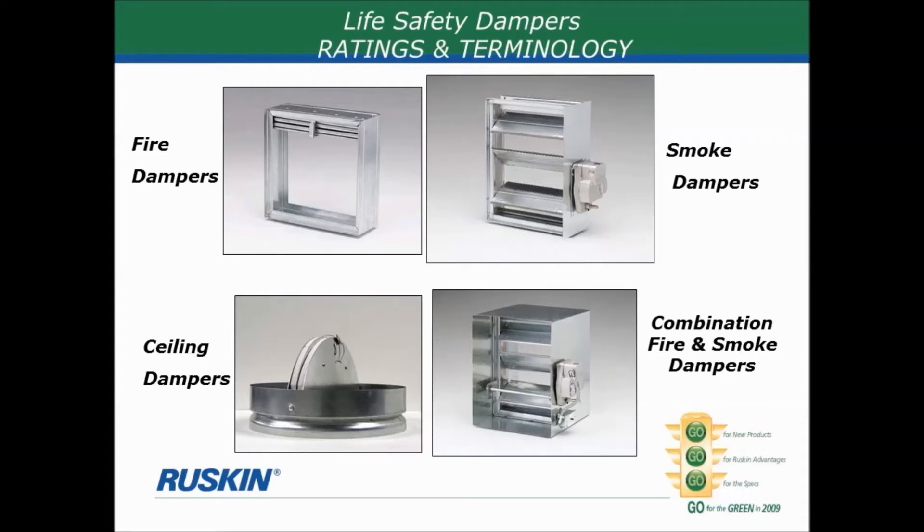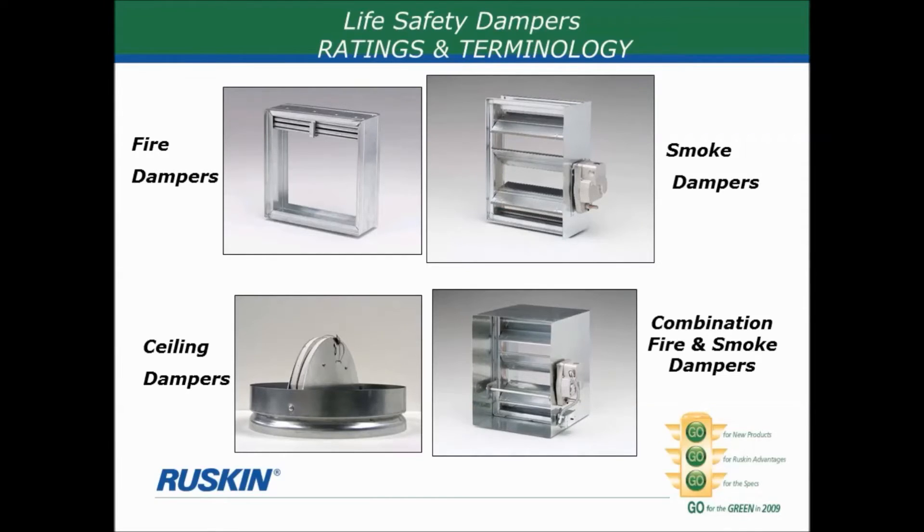Smoke dampers are always motor controlled. There may be a need to close a smoke damper even though the fire is located in a different part of the building — so there's no heat or flame at the damper position yet, but it still needs to close. The actuator motor that operates a smoke damper, like all life safety actuators, is power open — continuously driving the blades to the open position — and then spring return, fail closed. If smoke is detected, a signal cuts off power to the actuator and the spring cranks the blades to the closed position. Smoke dampers almost always come with blade seals and jamb seals to make it a tight fit so virtually no smoke can get through.